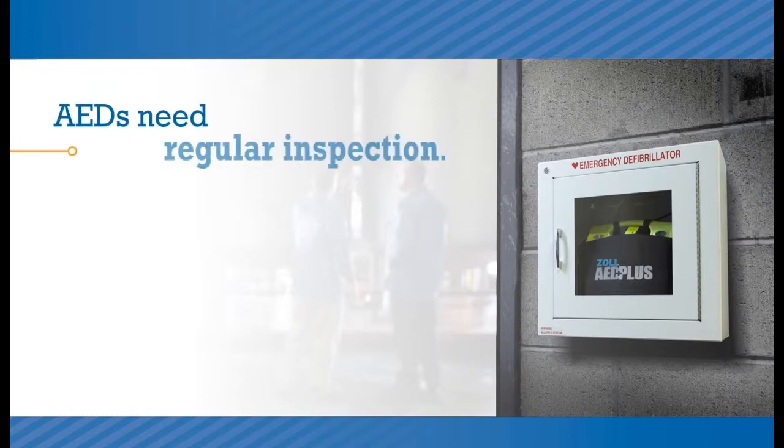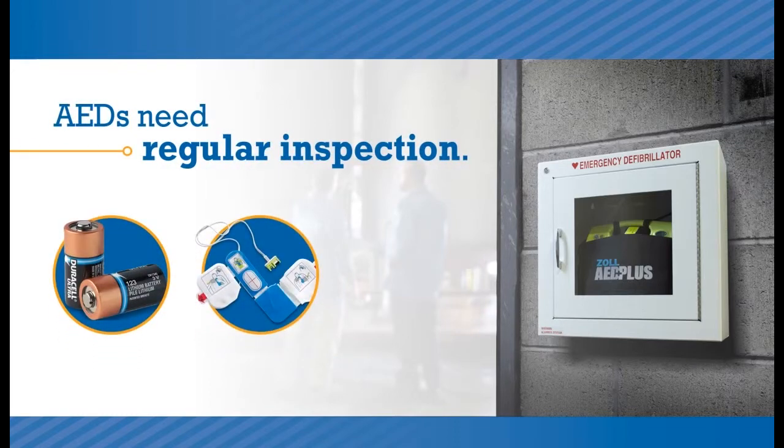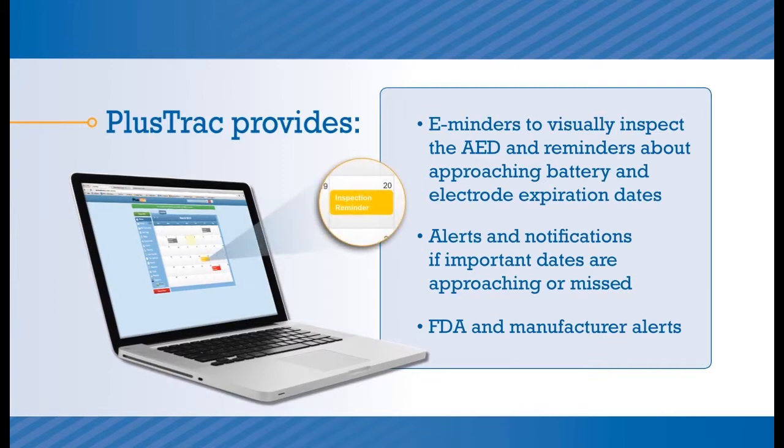AEDs need regular inspection. Batteries and the electrodes used to provide a shock expire over time. Through PlusTrac, the program manager at your site will receive email reminders to make sure everything is in good working order. PlusTrac will help you stay on top of all aspects of maintaining an AED program, including notifying you when consumables are nearing expiration, as well as making sure you're aware of any FDA or manufacturer alerts concerning your AEDs.